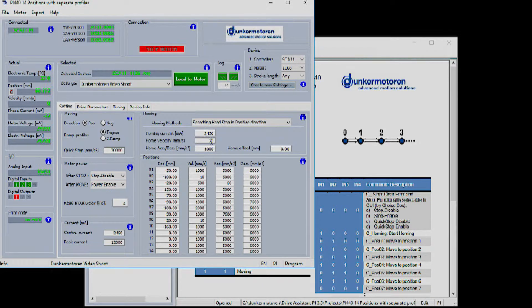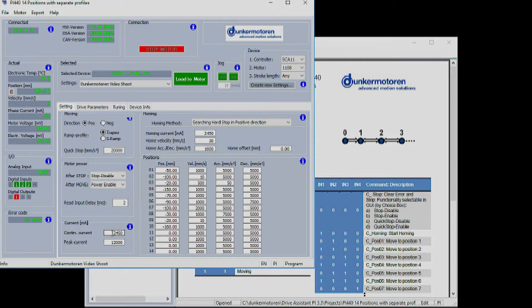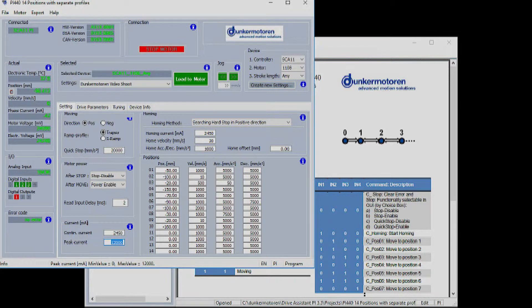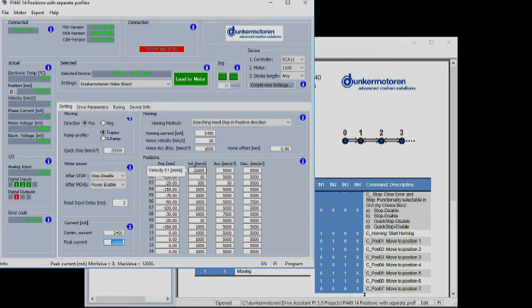The peak and continuous currents can also be controlled. Each motor has different continuous and peak currents and damage can be caused to the motor if these values are set too high. Please verify the currents in the specification of the individual motor you are currently using.